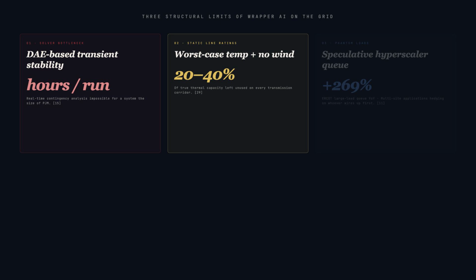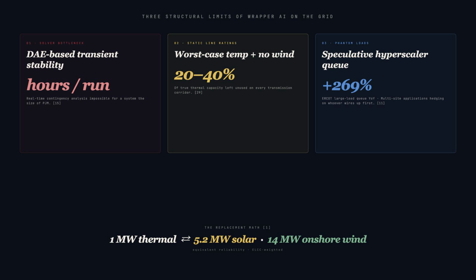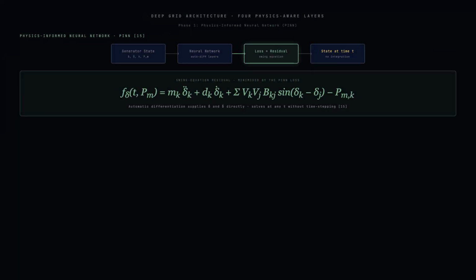A single transient stability simulation across PJM solved by traditional differential algebraic equation methods takes hours, so real-time contingency analysis is impossible. Static line ratings on transmission corridors are calculated under worst-case temperature and wind assumptions, leaving 20 to 40% of a line's true thermal capacity unused. The interconnection queue is clogged with phantom loads, speculative hyperscaler applications across multiple sites, hedging on whichever utility wires up first. And the replacement math is brutal. Replacing 1 megawatt of retiring thermal generation requires roughly 5.2 megawatts of solar or 14 megawatts of onshore wind to maintain equivalent reliability. Veriprajna's answer is not an AI wrapper.